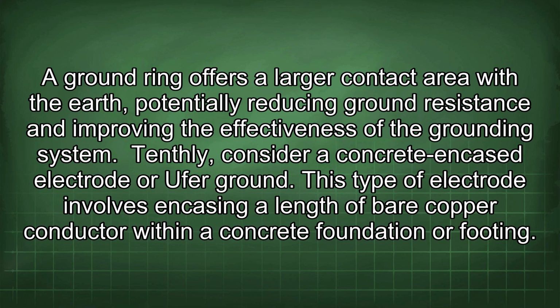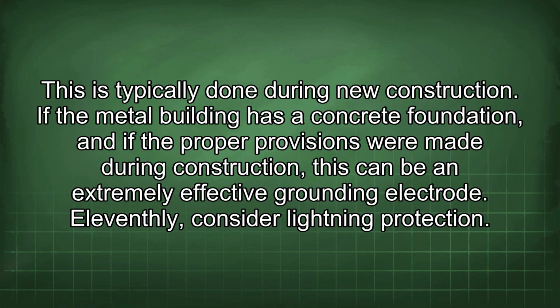Tenthly, consider a concrete encased electrode or UFER ground. This type of electrode involves encasing a length of bare copper conductor within a concrete foundation or footing. This is typically done during new construction. If the metal building has a concrete foundation, and if the proper provisions were made during construction, this can be an extremely effective grounding electrode.